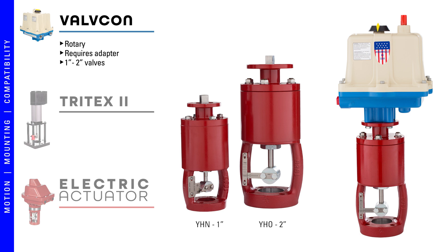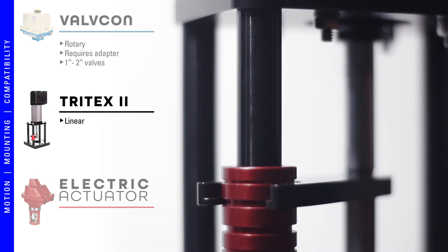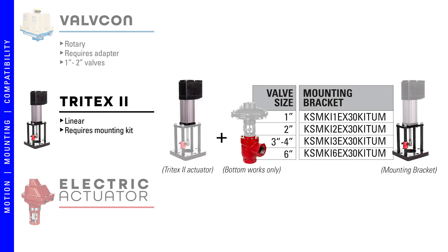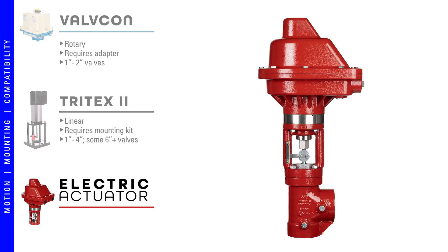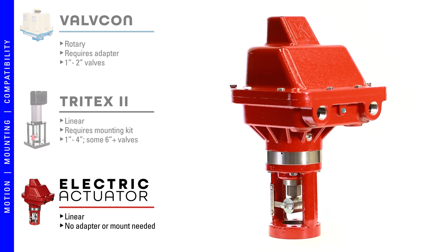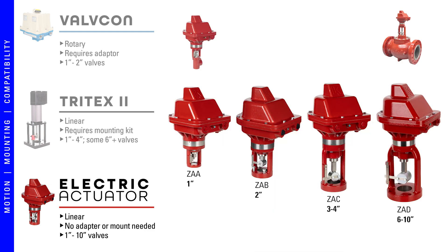The Valvcon is ideal for most applications with one to two inch valves. The Tritex is a linear actuator and actuates in a straight line up and down. However, it also requires a mounting kit that comes in various sizes depending on your valve body. It is available for all Kimray high pressure control valves from one to four inch and can be used on some six inch and larger valves. The Kimray electric actuator is also a linear actuator, meaning you can install it directly on a linear globe valve like the Kimray high pressure control valve body, with no adapter or mount needed. It works on all control valve bodies from one to ten inch and is simplified to four options based solely on the valve body connection size.